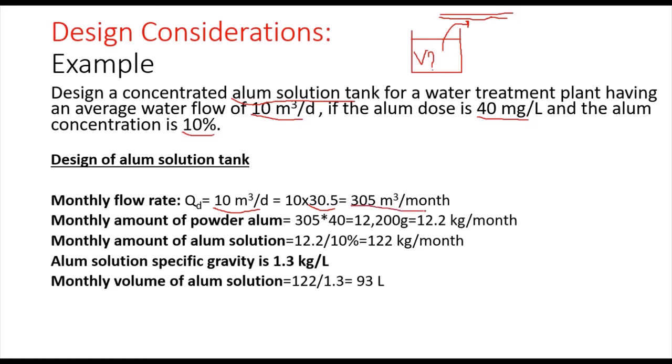So we are treating 305 cubic meters of water every month. Now the amount of powder alum will be 305 times 40, which is the alum dose. We will get 12,200 grams, which is equivalent to 12.2 kilograms per month. The monthly amount of alum solution will be 12.2 divided by the 10%, so we will need 122 kilograms per month. So here you will have an idea also about the cost of the alum powder.